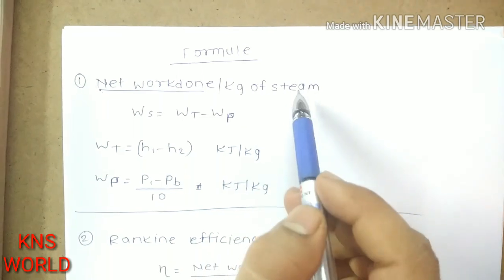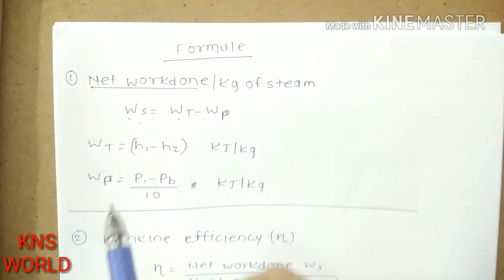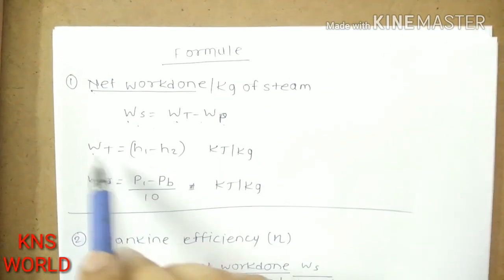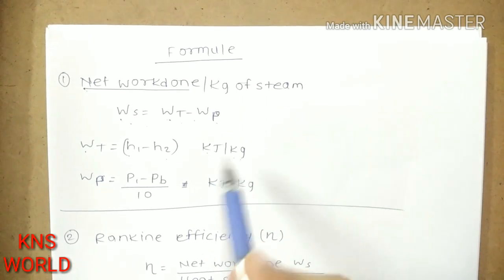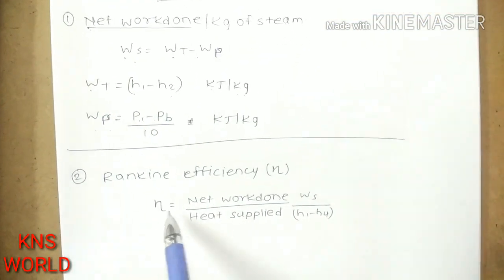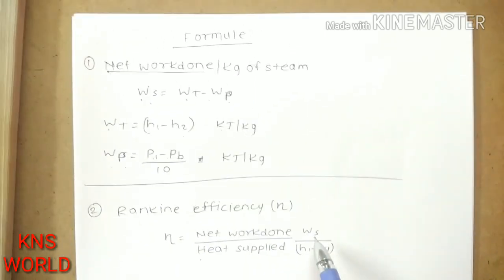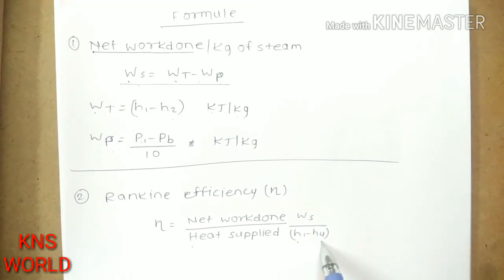We need some formulas. First, net work done per kg of steam: Ws equals turbine work Wt minus pump work Wp. Turbine work is H1 minus H2 kJ per kg, and pump work is P1 minus PB divided by 10. For Rankine efficiency, it is net work done divided by heat supplied, which equals net work done divided by H1 minus H4.